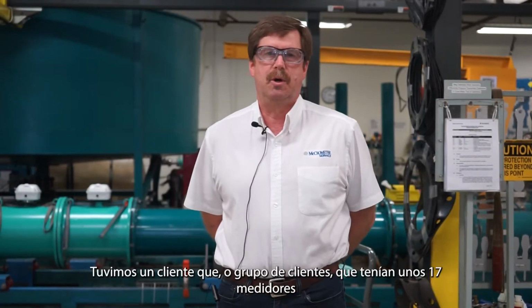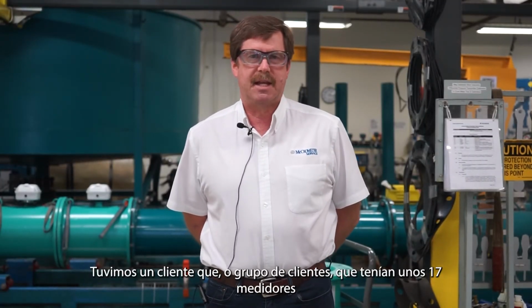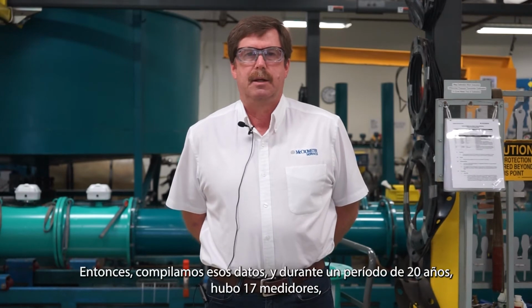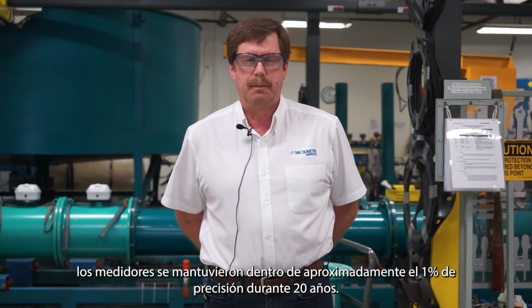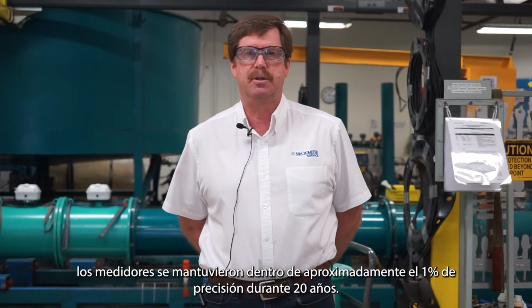We had a customer, or a group of customers, that had about 17 meters, and the EPA was requiring them to recalibrate periodically. So we compiled that data, and over a 20-year period, there were 17 meters. The meters stayed within approximately 1% accuracy over 20 years.